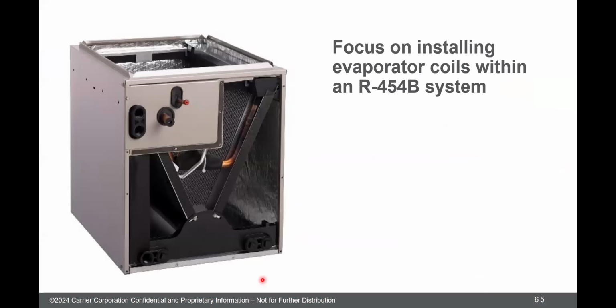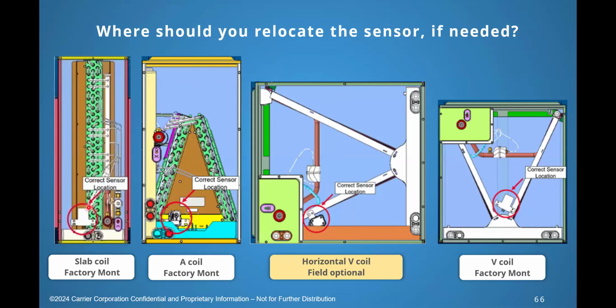There is one time they're going to have to move the sensor. The sensor is factory installed in the evaporator coil on a slab, a V coil, A coil. It's factory installed on there. In some cases, we have coils that are what we call multi-poise, meaning you can run them vertically, air moves through them this way, or horizontally, air moves this way. So this one here is a multi-poise. There's a drain pan here and a drain pan there. The sensor needs to be at a low point of the coil. If you did not know it, refrigerant is heavier than air.